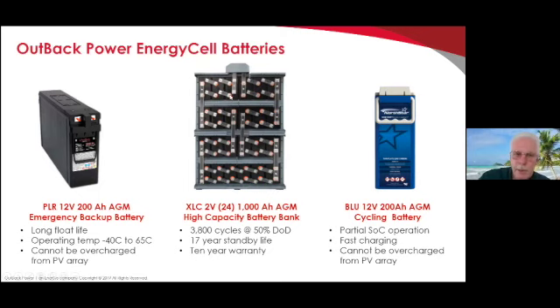The XLCs are a really awesome battery if somebody needs a lot of kWh. They have specifications approaching lithium-ion batteries — 3,800 cycles at 50% depth of discharge, which is pretty top end for an AGM battery, a 17-year standby life, and a full 10-year replacement warranty, as long as the batteries are part of a battery monitoring system that's logging all the charging data and stuff.